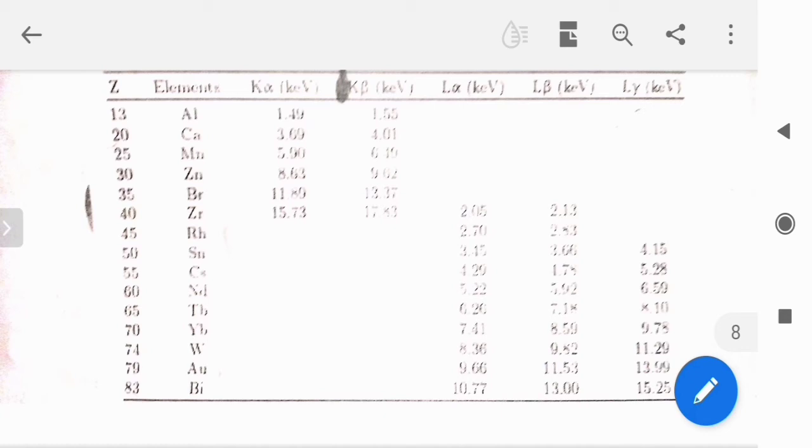Okay, so that is the qualitative analysis based upon the standard X-ray emission energy. We can compare this standard X-ray emission intensity and get the idea about the qualitative analysis. Qualitative analysis is generally used for the specific elements which are characteristic for that particular element. The X-ray energies of interest lie below 20 kilo electron volt. So for most of the elements that energy lies below 20 kilo electron volt, when the elements are lighter in mass.